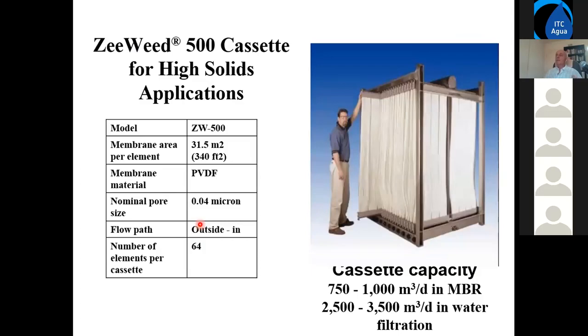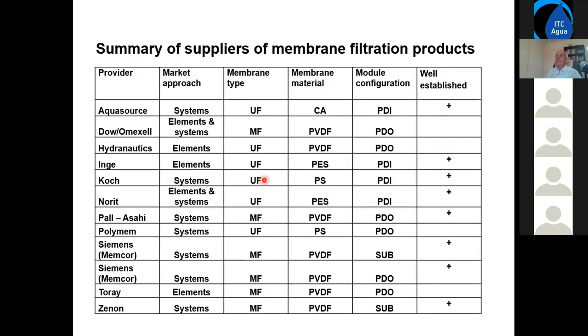Those are the fibers we use mainly for the MBR. Those are very strong fibers. They are supported, so then everything else was self-supported. Those fibers have the polyester insert, on top of which we have the membrane. The membrane is PVDF. The majority of the membrane manufacturers still have this old name.